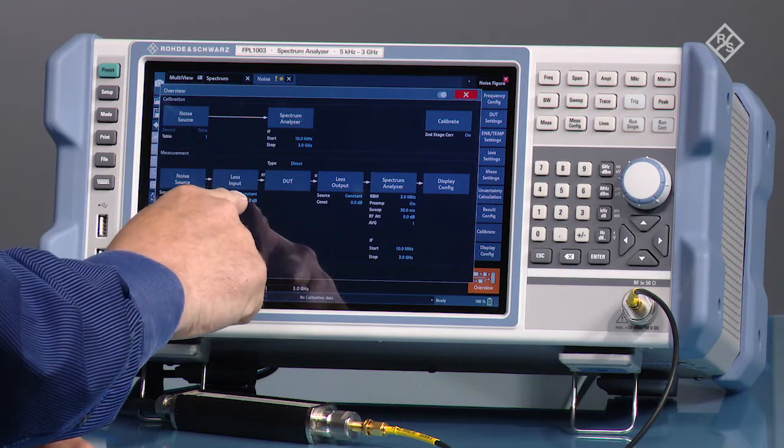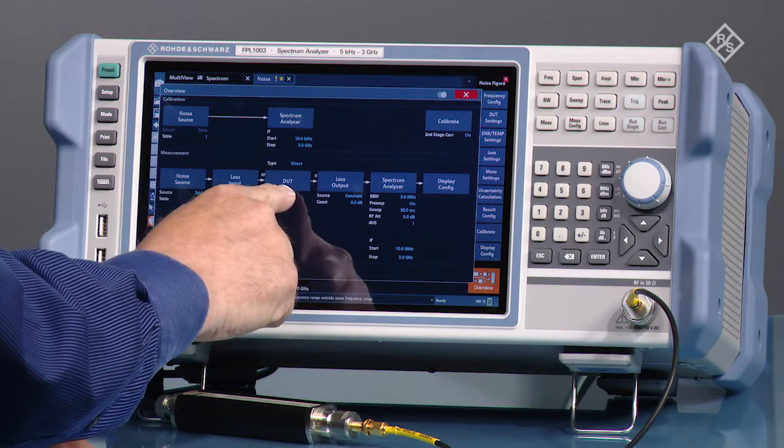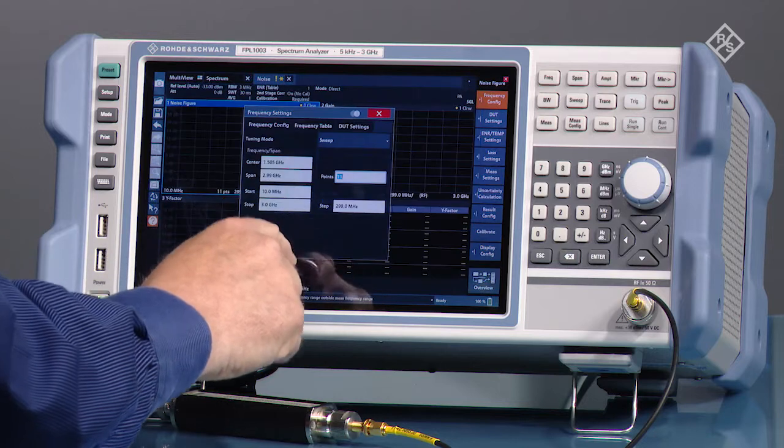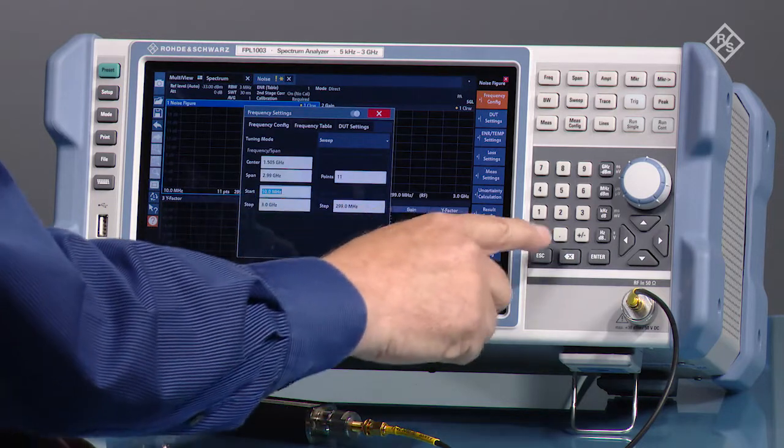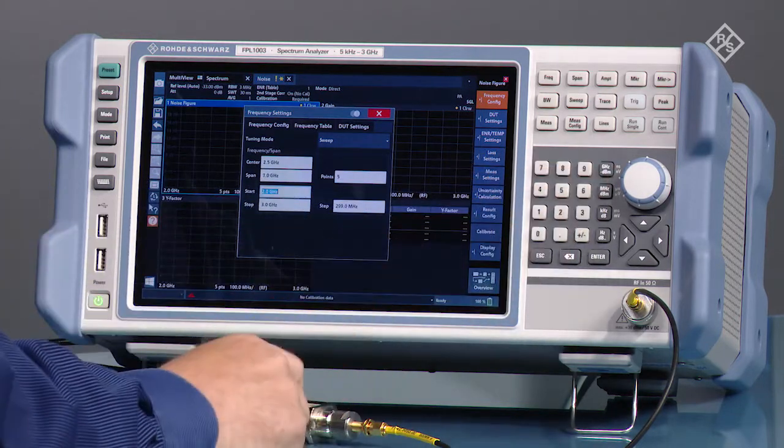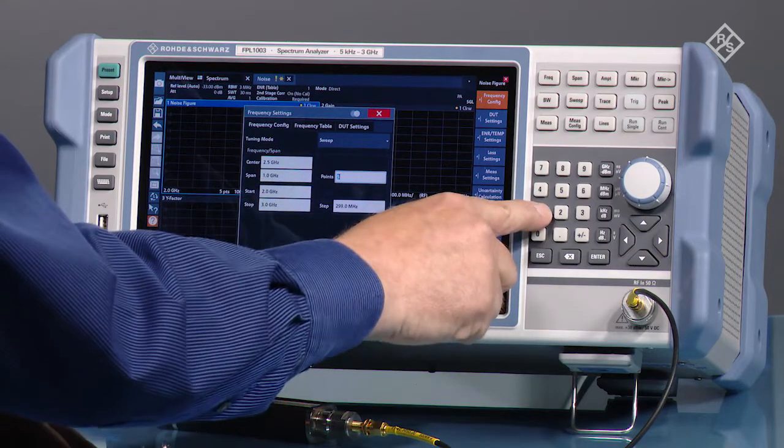We could enter loss input if we needed to but for this device we're not going to do that. Now we're going to go to DUT. We're going to set the frequency at 2 GHz to start and the number of points to 11.